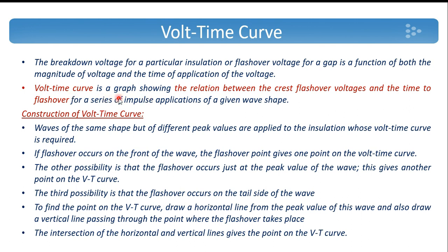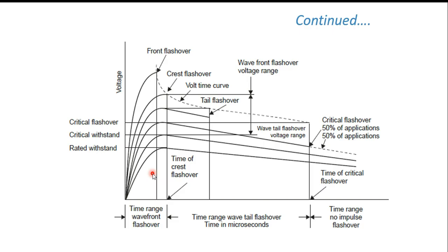The volt-time curve is a graph showing the relation between crest flashover voltages and time to flashover. For constructing the volt-time curve, waves of the same shape but different peak values are applied to the insulation and the flashover voltage is found out. Different waves with different peak magnitudes of the same shape are applied to the insulation and the time and voltage at which flashover occurs is measured. The flashover can occur at the front of the wave, at the peak point of the wave, or at the tail of the wave — three possibilities for flashover.